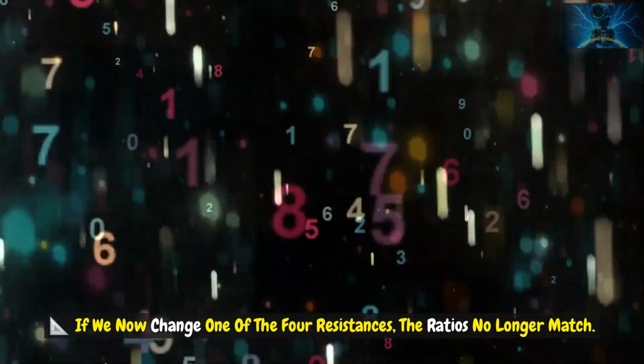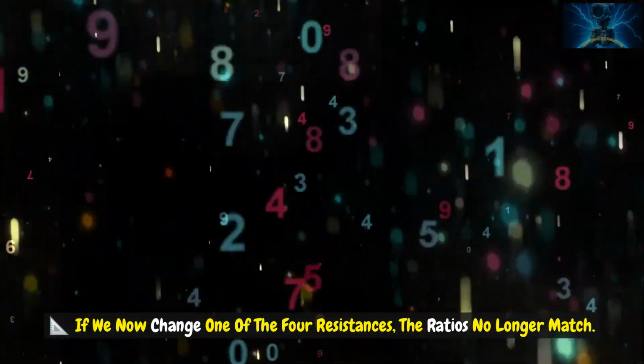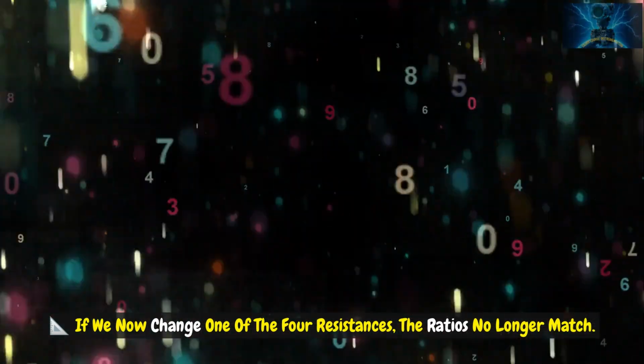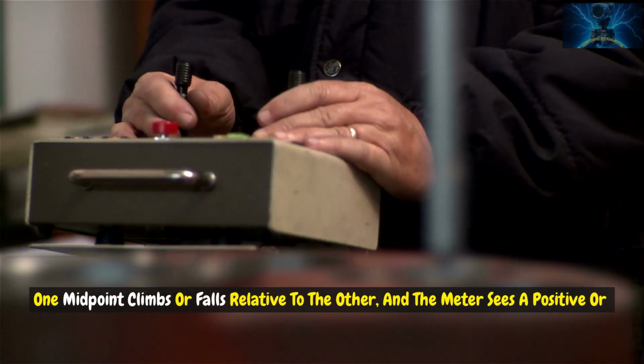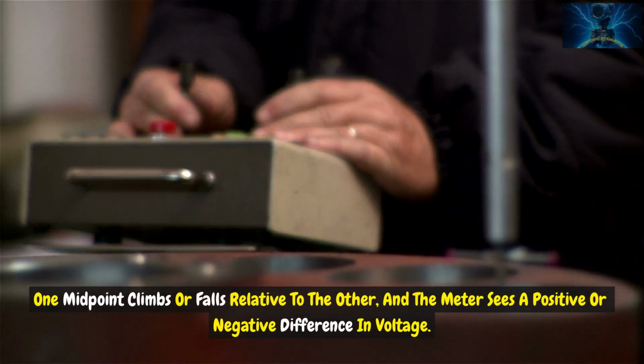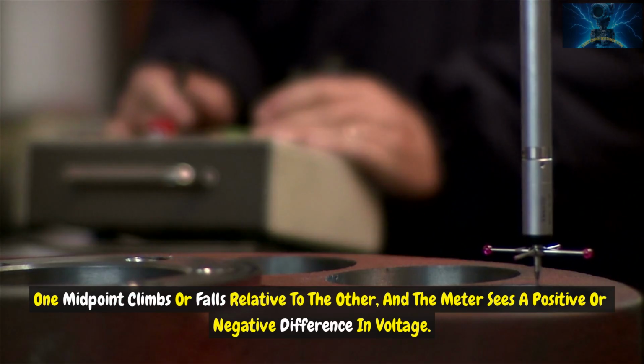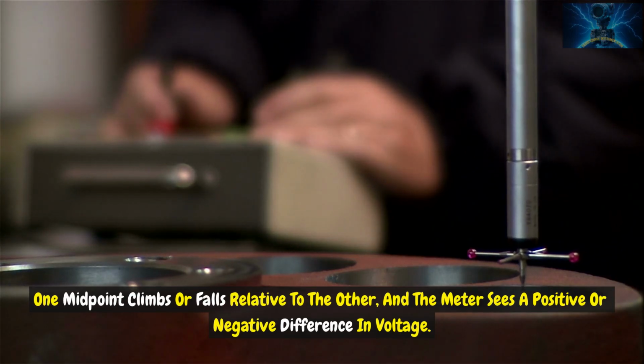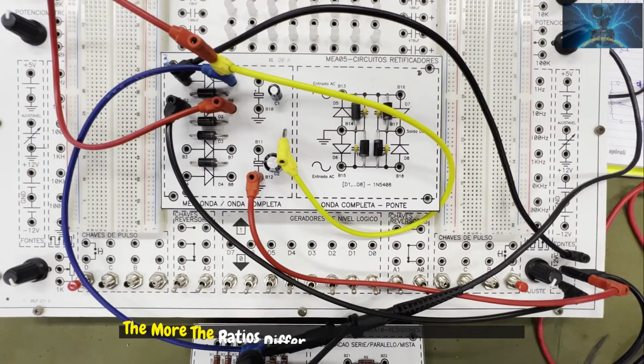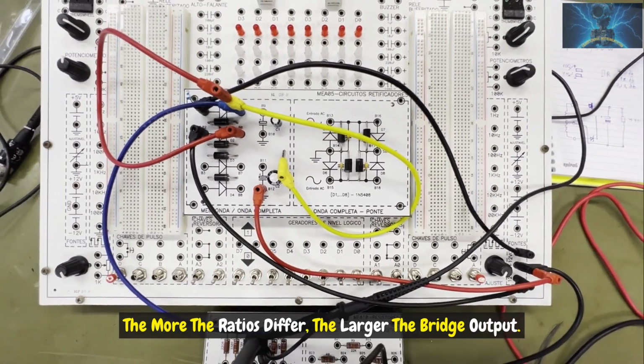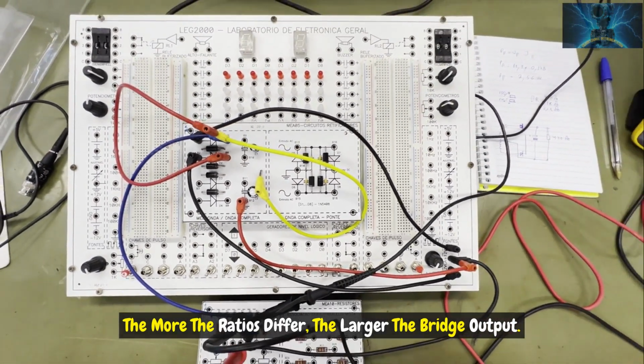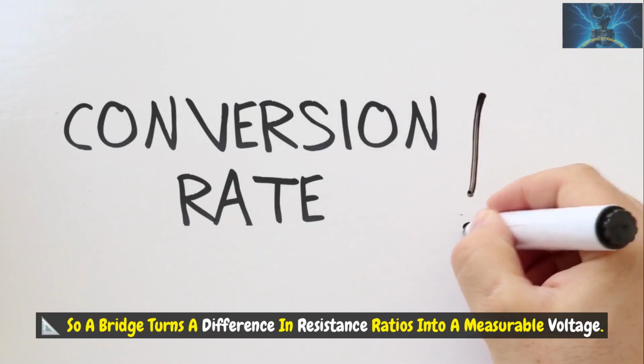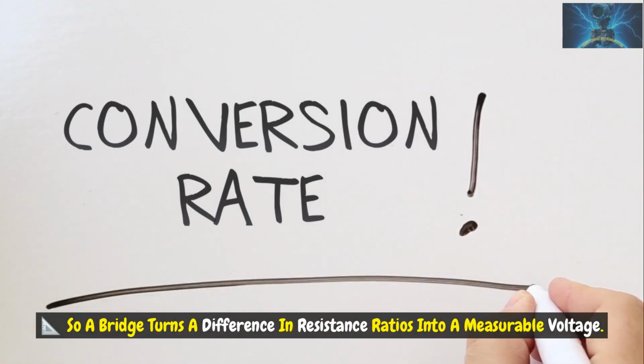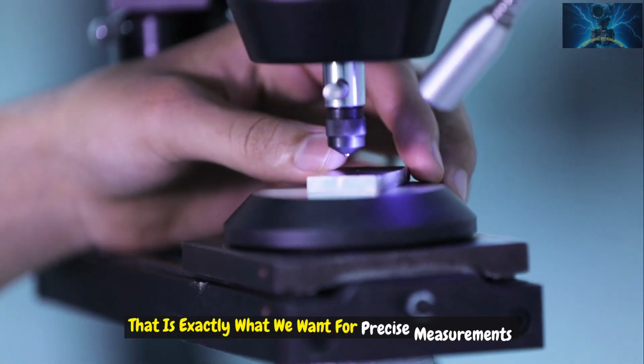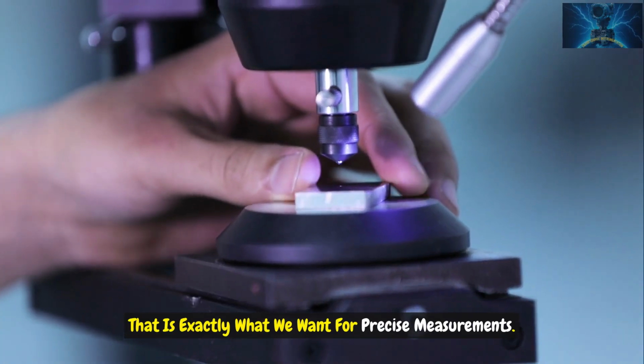If we now change one of the four resistances, the ratios no longer match. One midpoint climbs or falls relative to the other, and the meter sees a positive or negative difference in voltage. The more the ratios differ, the larger the bridge output. So a bridge turns a difference in resistance ratios into a measurable voltage. That is exactly what we want for precise measurements.